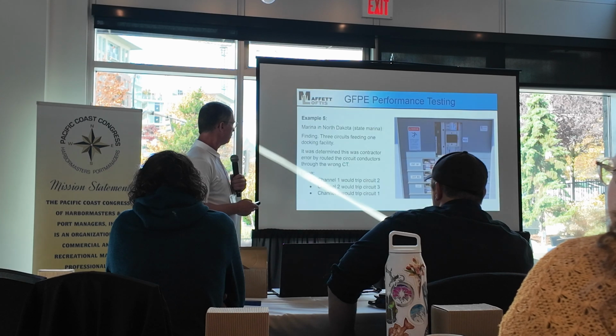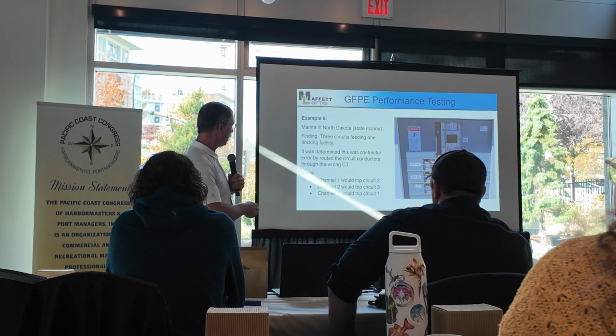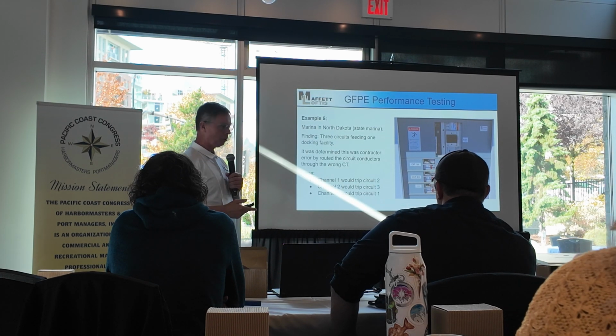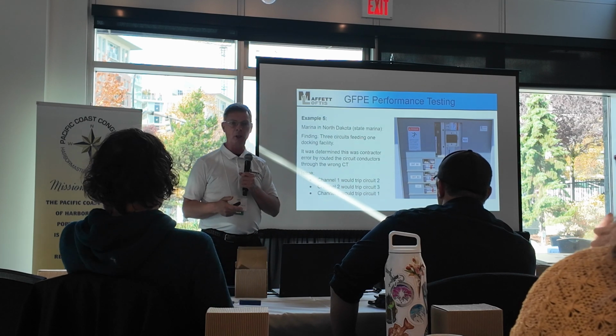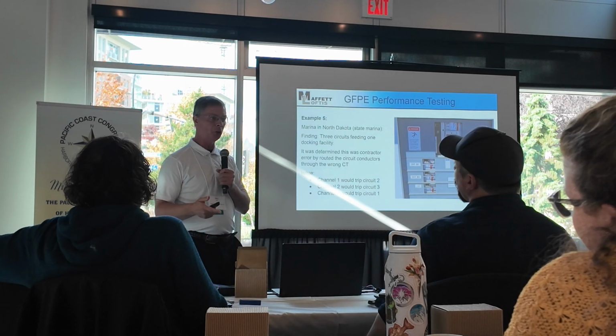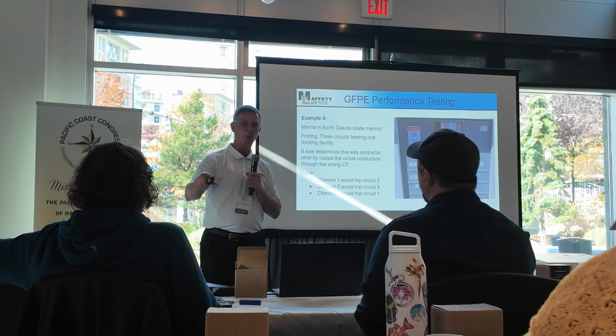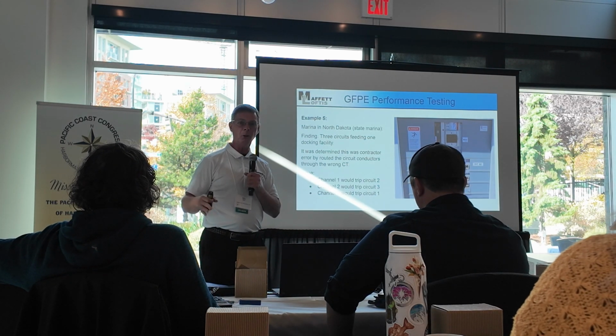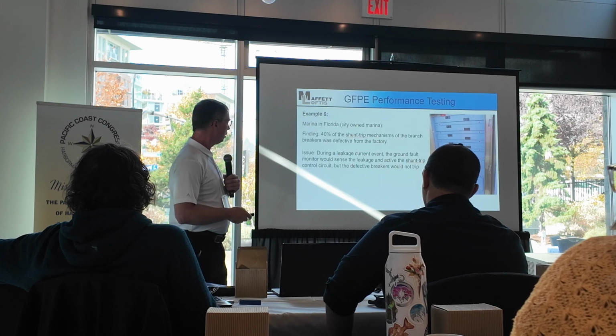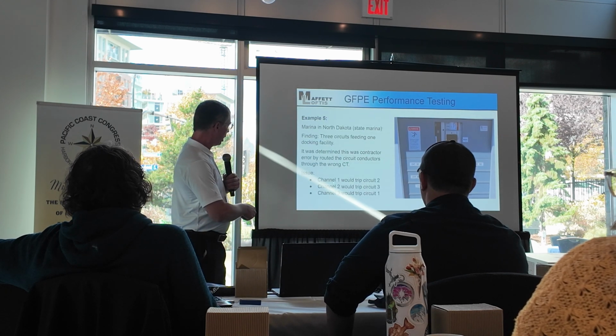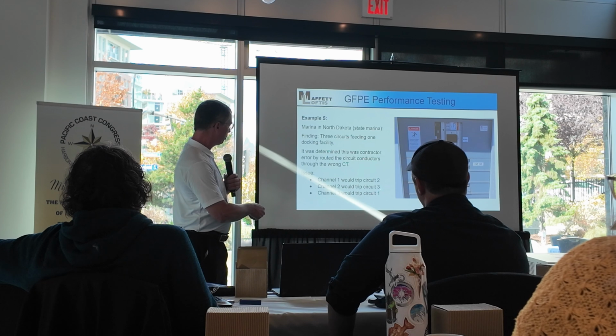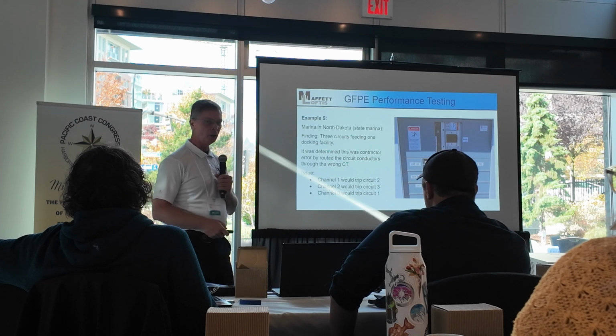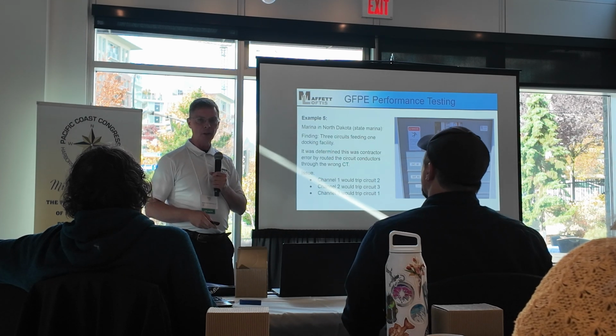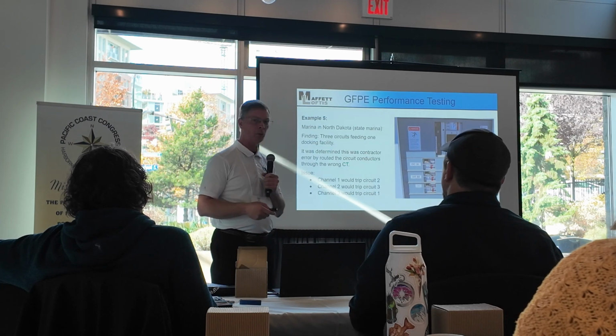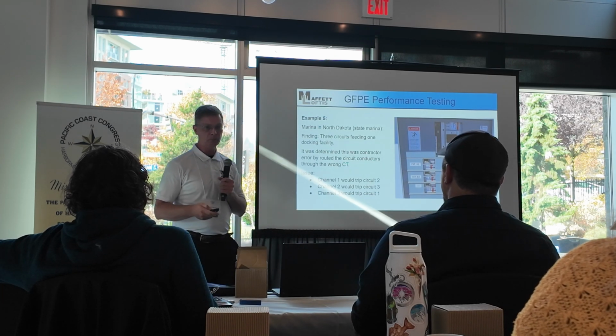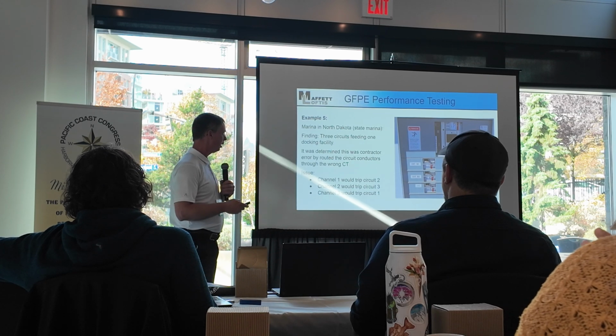And in this case, this was actually in North Dakota. And this was about a 6 or 7 year old marina when I was doing some renovations to it, and the harbor master said, Gary, why don't you come over here and just test this one for me? I said, oh, sure, I'll just do that, no problem. Well, it wound up, channel 1 would trip channel 2, channel 2 would trip channel 3, and channel 3 would trip channel 1. None of it was wired correctly. So if you have a leakage current anywhere in that marina, your breaker was not going to trip. So you'd go out there and get electrocuted just at that.